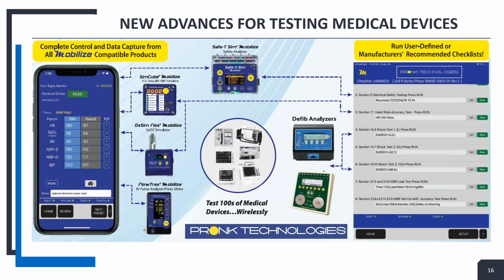It knows the pass-fail requirements for the electrical safety test, and it instructs it to go ahead and run the test. So the procedure is not just a text procedure, it's got programming in it that tells the equipment, do the test according to the requirements that either you've designed or following the manufacturer's requirements.